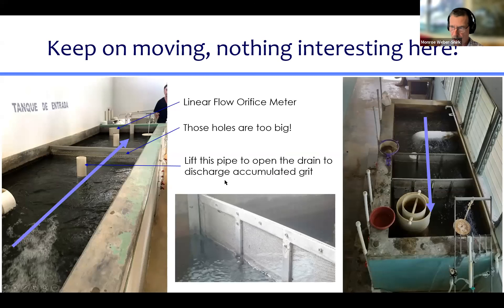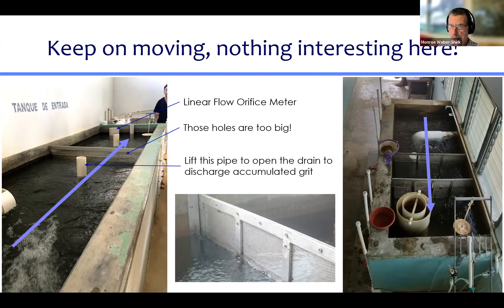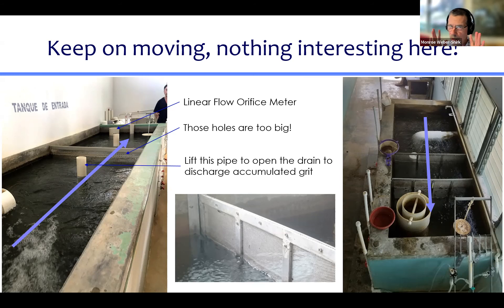Here are pictures from real AguaClara plants. The one on the left is at Moroceli - that's the town with the river as a water source shown in an earlier class. Something bothers me right away: the trash rack holes look pretty big, and I'm pretty sure they're bigger than they should be. The holes have to be smaller than anything likely to cause a problem downstream - there's a restriction in the clarifier of about four millimeters, so the holes ought to be four millimeters or smaller. Those holes look more like a centimeter, so they're too big - things we're still learning.